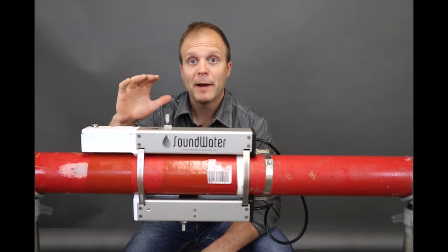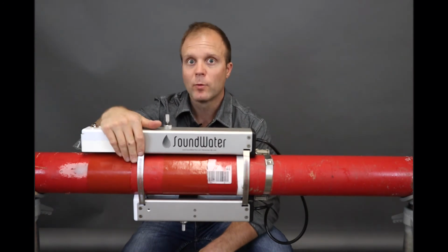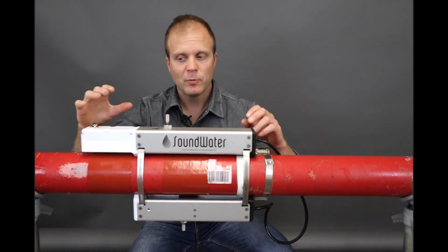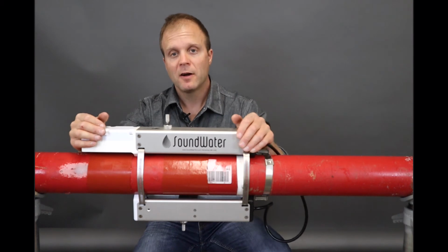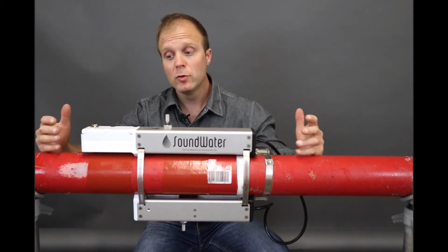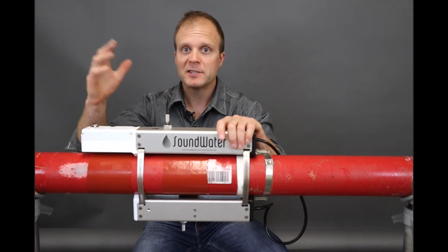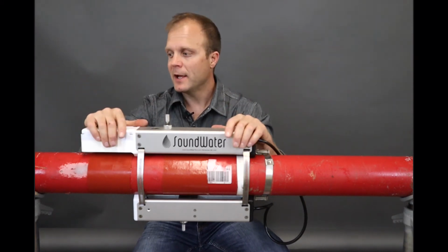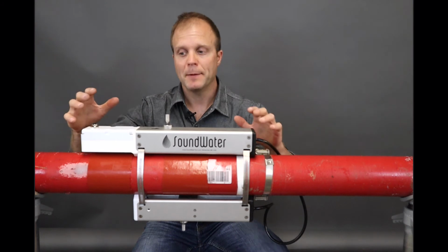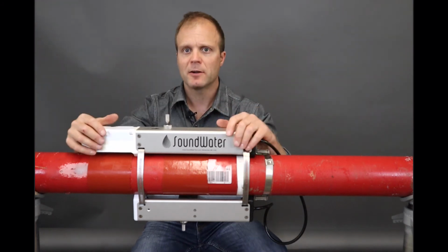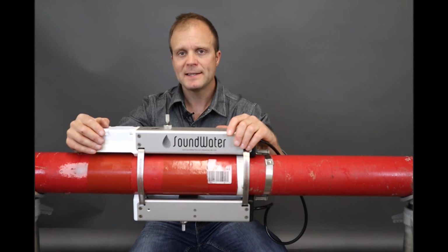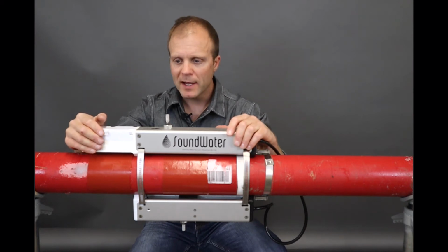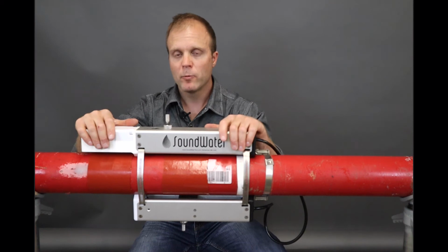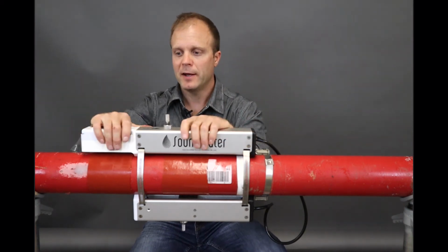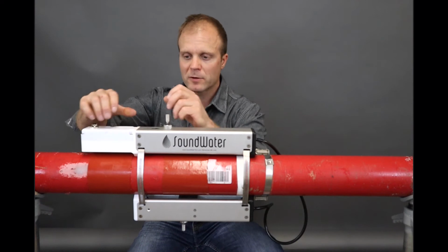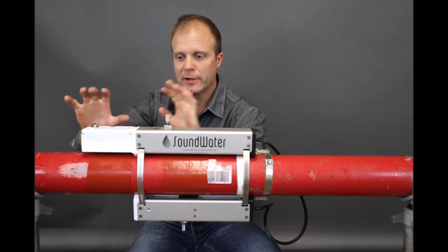Okay, quick comment about how tight do we make these straps? Well, the goal is to make sure this thing is going to be secured on the pipe and does not move over time, temperature variations throughout the day and the seasons, and with any mechanical vibrations in the pipe. So there needs to be some preloaded tension on this flow meter to sort of stay tight through all those conditions. And we don't want to damage anything. So we certainly don't want to have a torque wrench or socket wrench with a long handle and give it all you got. Okay, don't do that.